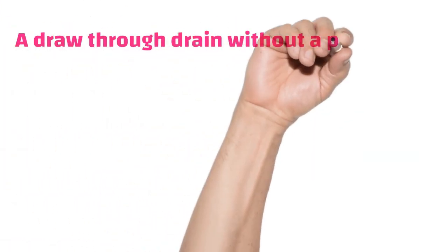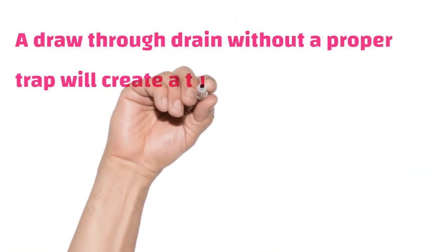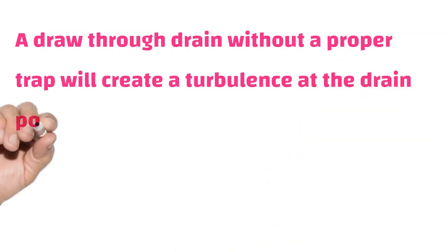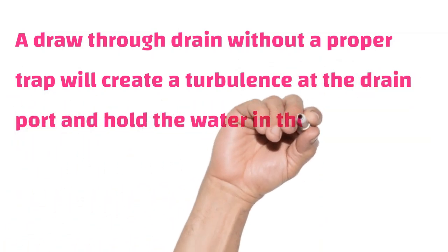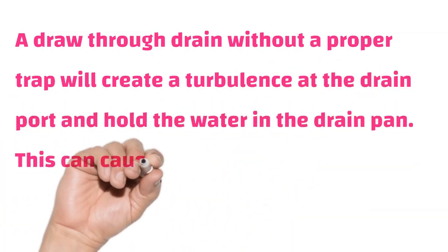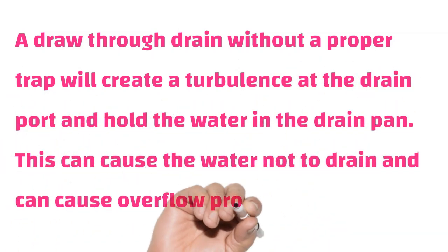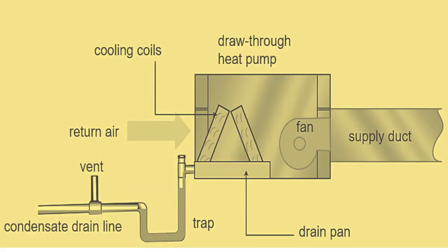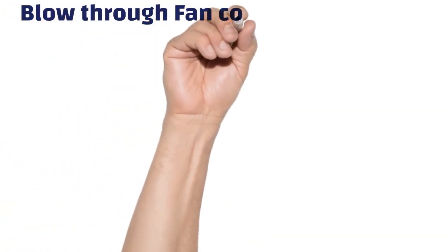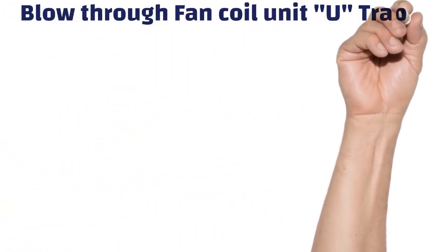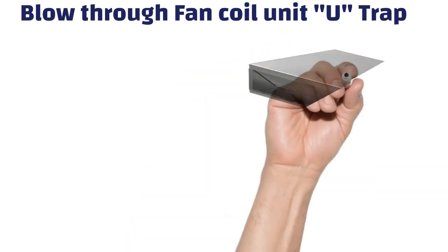A draw-through drain without a proper trap will create turbulence at the drain port and hold the water in the drain pan. This can cause the water not to drain and can cause overflow problems.